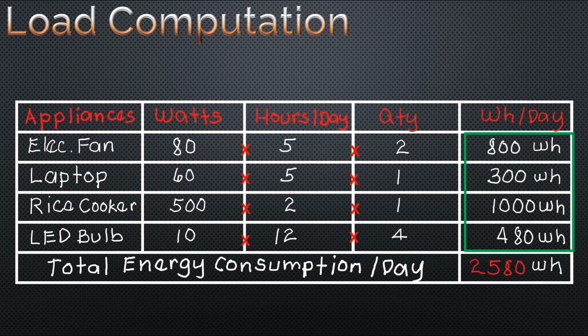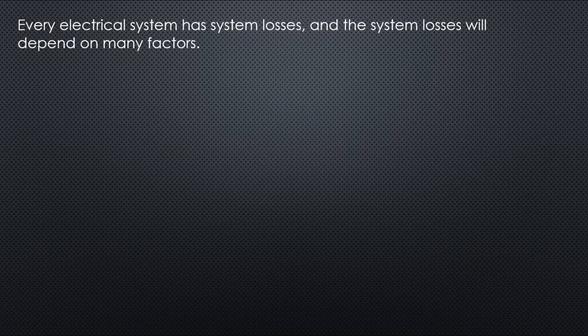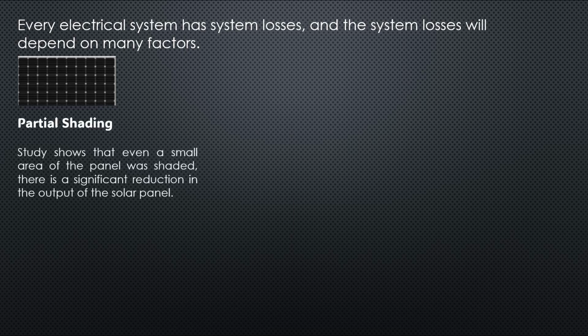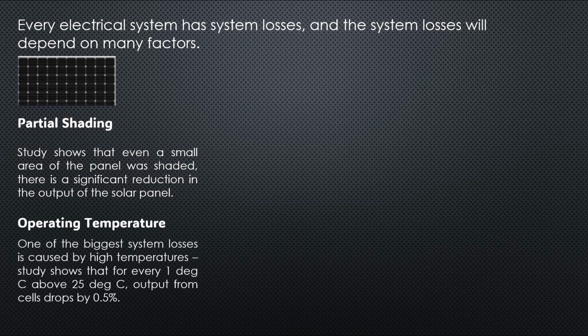But in supplying this total energy from the source, which is the solar panel, we need to consider the power losses of each piece of equipment, like the solar panels, inverter, and wires, before it reaches the loads. You need to remember that every electrical system has system losses, and the system losses will depend on many factors. For example, in the solar panels, there are many factors that can affect the performance of the panel. First is partial shading, like for example, the shading coming from nearby trees or any structures. Another factor that significantly affects the output is the operating temperature.